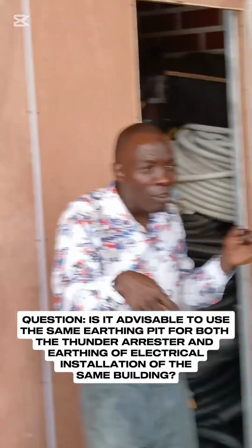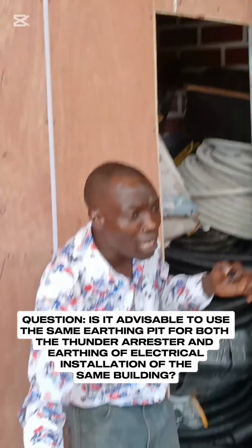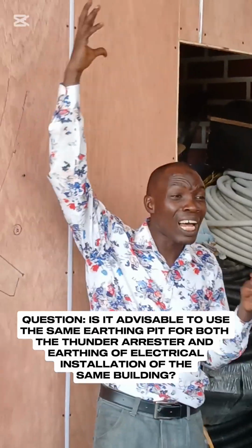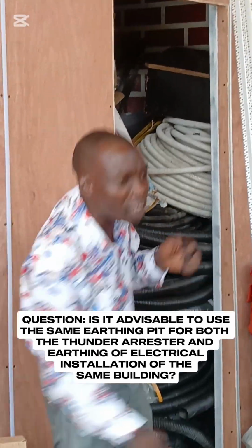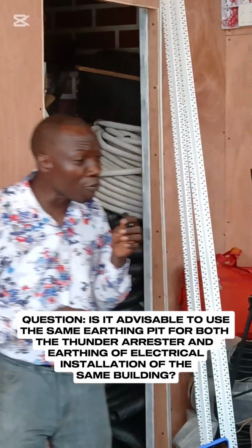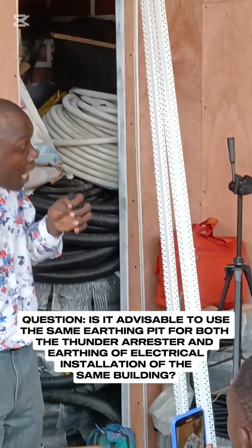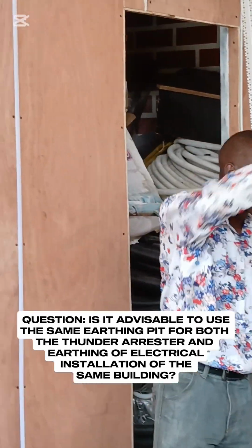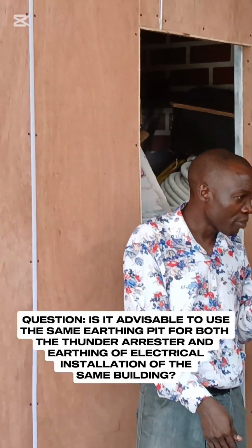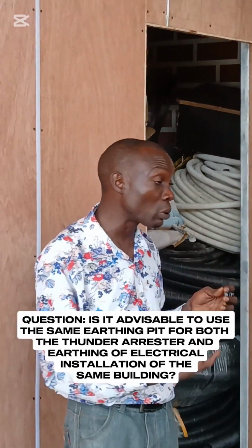But if you now pick your earthing for your electrical installation from the same pit, which means as that high voltage is grounded, it will flow back into your installation and destroy it. So it's like you have created another path for that fault current to flow back into your installation. Try to create distance between them before you earth them. You can even choose different locations.